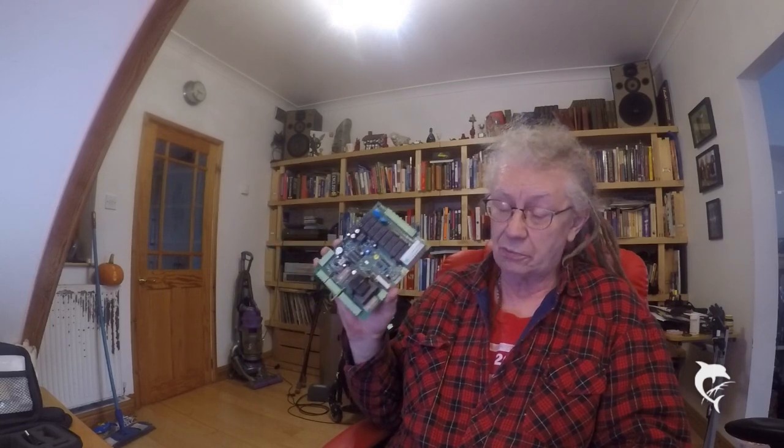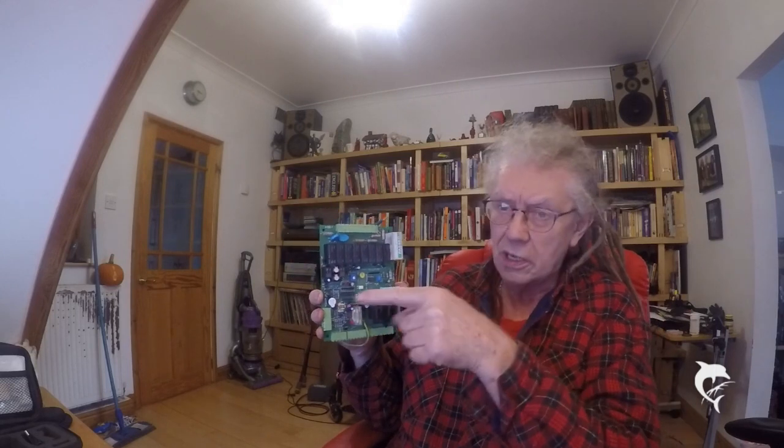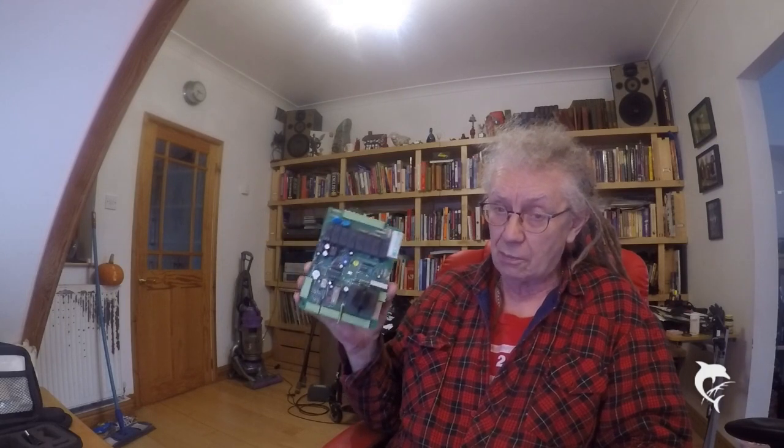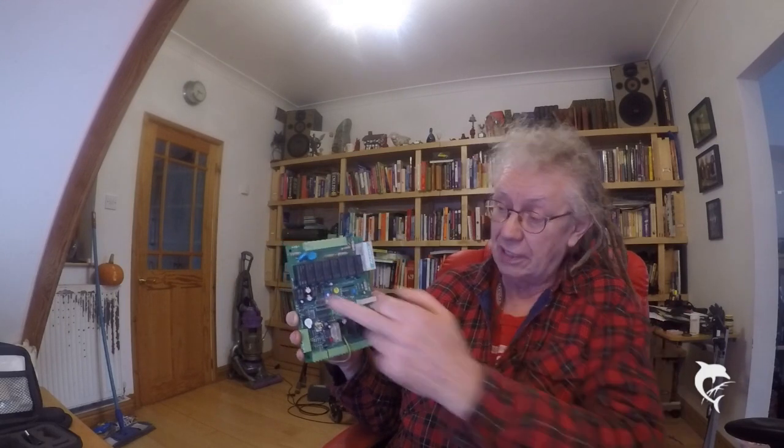It's always the same with a board with a load of electronics on it. You always assume that it's something clever in the electronics. I've been caught out by this time and time again. It usually isn't something in the electronics, and if it is, it's pretty obvious because things blow up. You're far more likely to get faults in things like relays unless there's a visible fault on the board. So this has caught me out, but it hasn't caught me out this time.